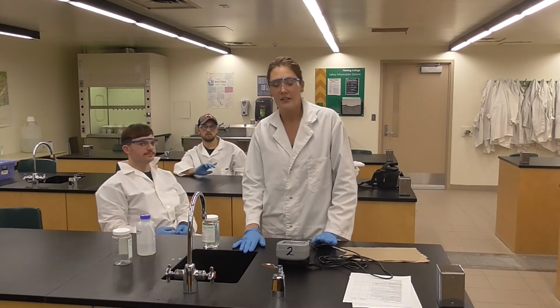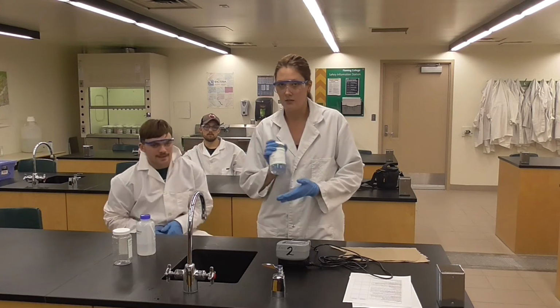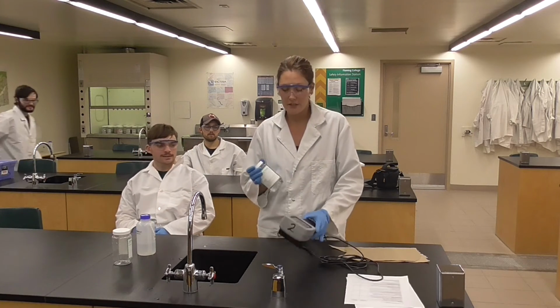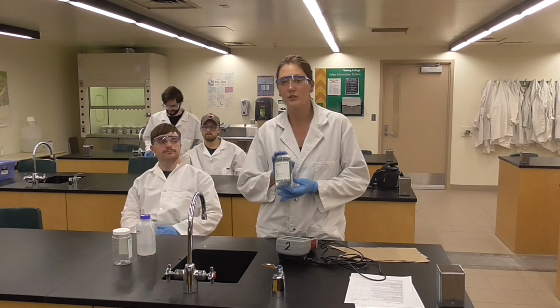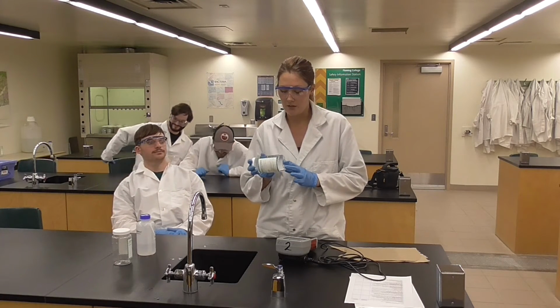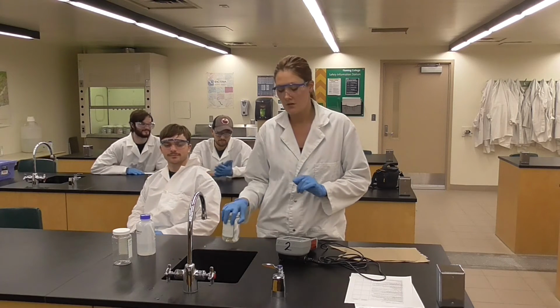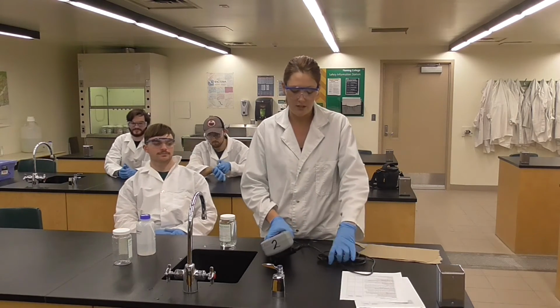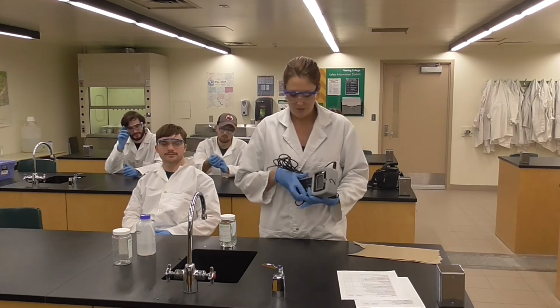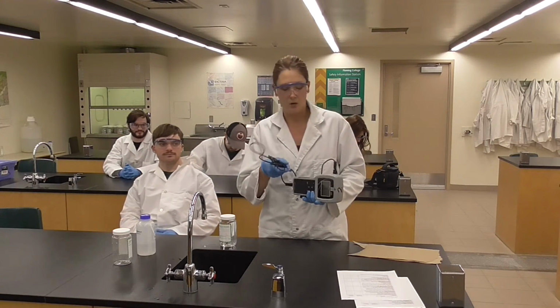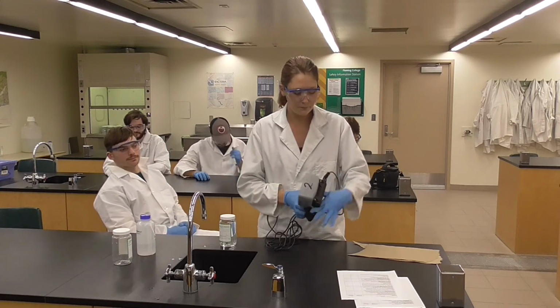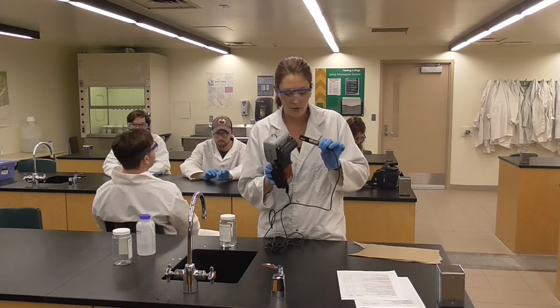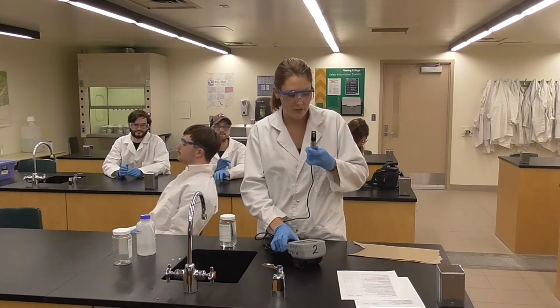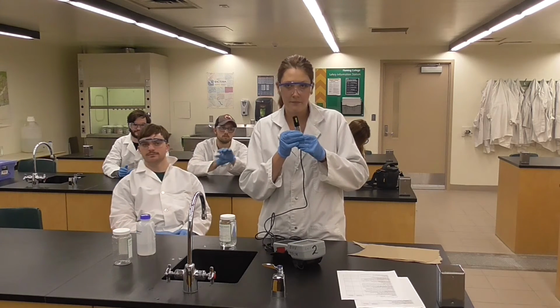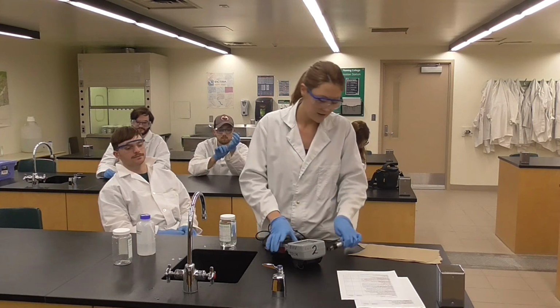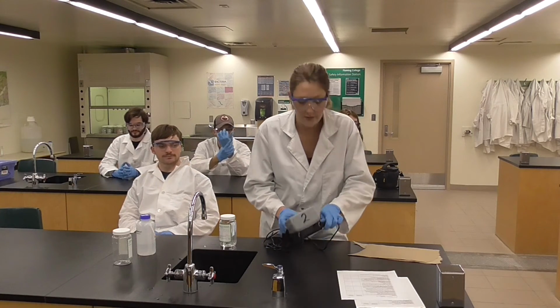Hi, I'm Janet, and I'm going to be talking about part 2 of the DO calibration with the DO meter. Will has already gone through and found out the concentration of the sample, so we're going to be testing that. So first, we check the overall condition of the machine, just to make sure that there's no cuts or anything in the wires, make sure it's all going to work properly. And the probe, that there's no damage done to it, there's no air bubbles or anything in there. Appears clean, looks good, so the housing's all good, so it can just stay in there.